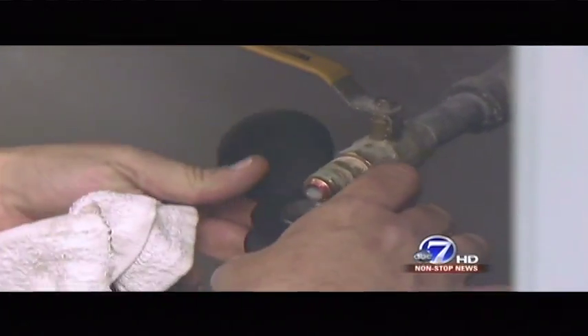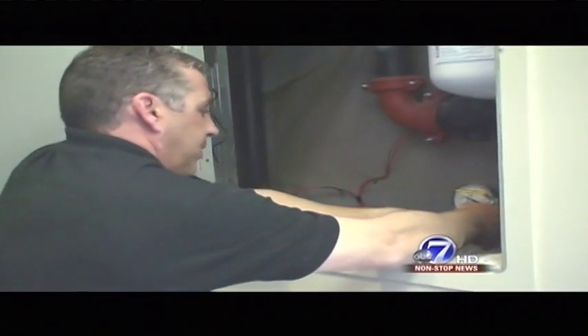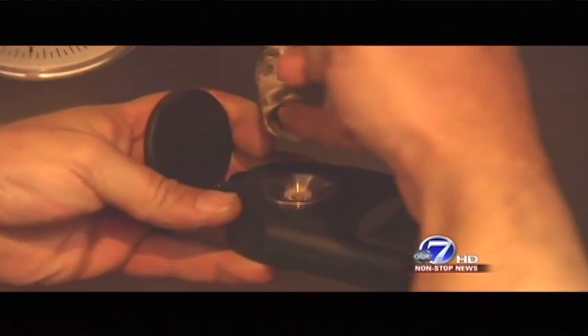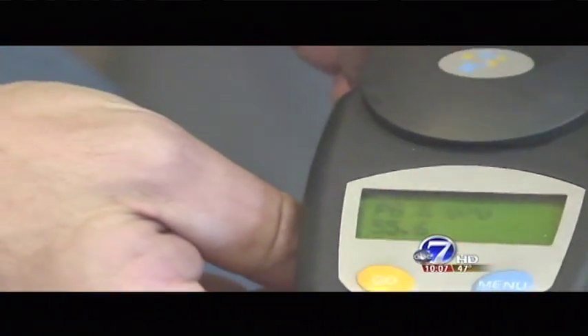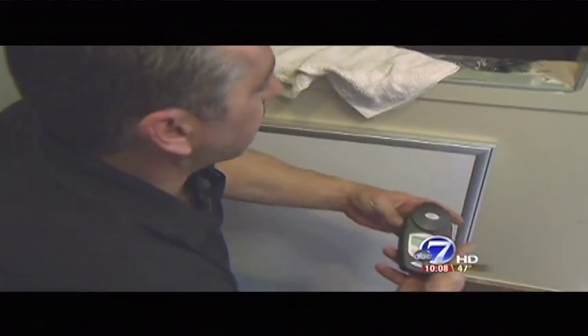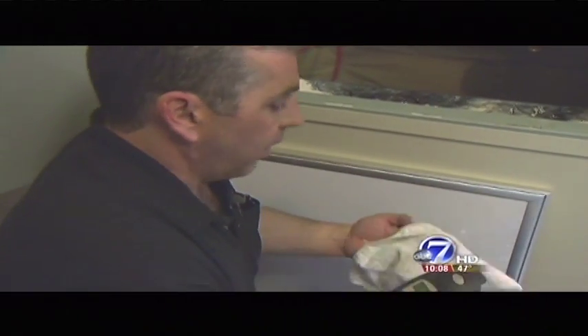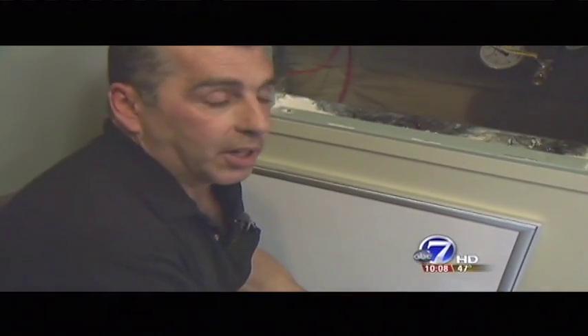I'm just getting a little sample of antifreeze out. On this day, he's testing a system with propylene glycol. It's supposed to have no more than a 40% concentration of antifreeze in the line. 55.6%. So on this particular system, we're 15.6% over.